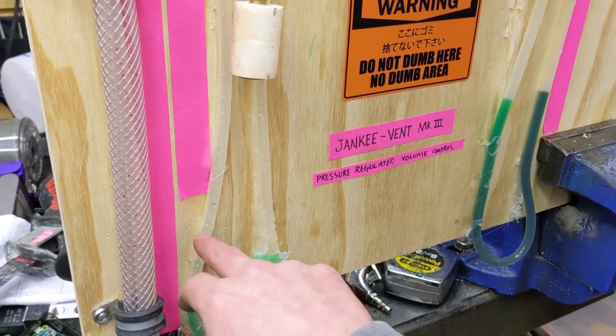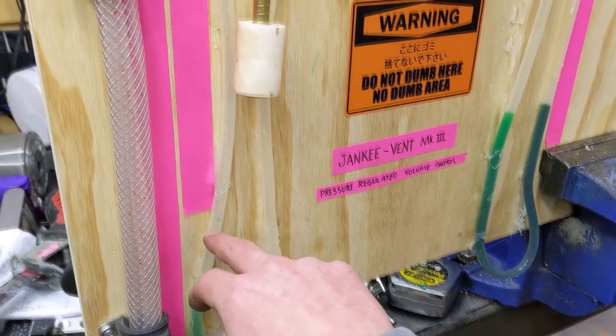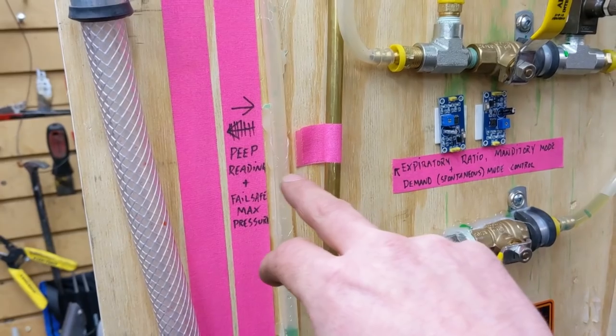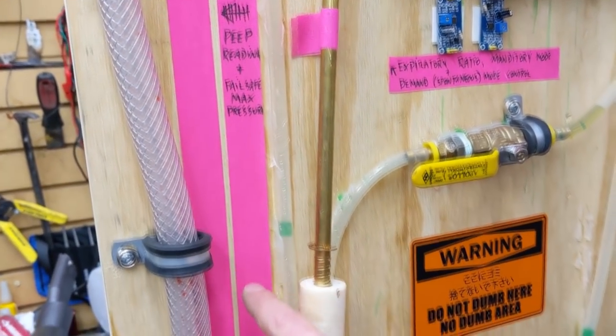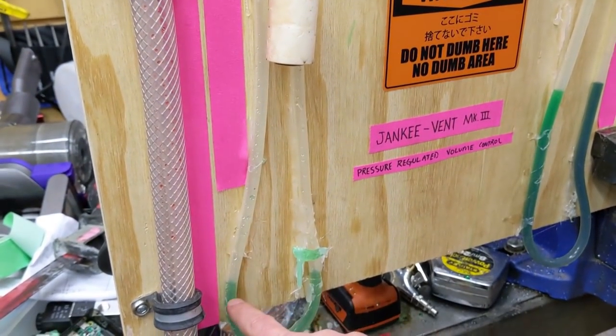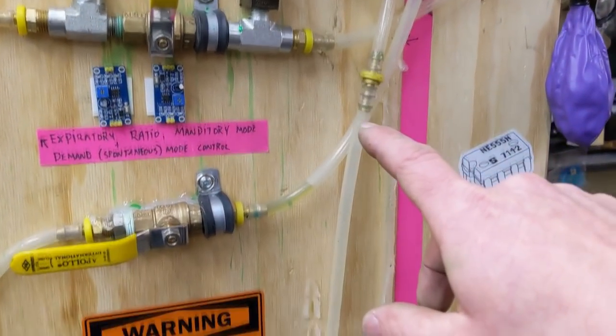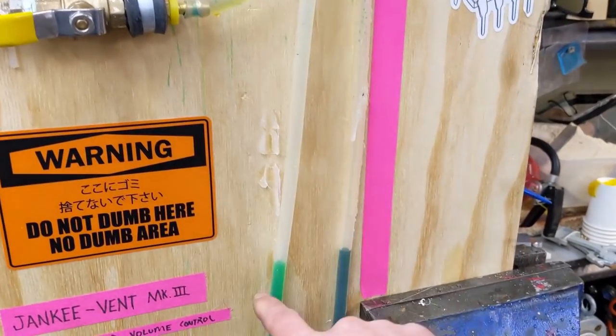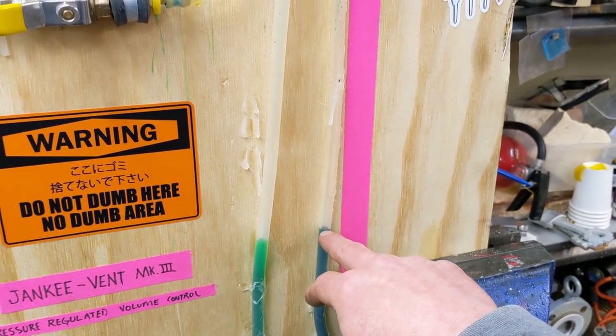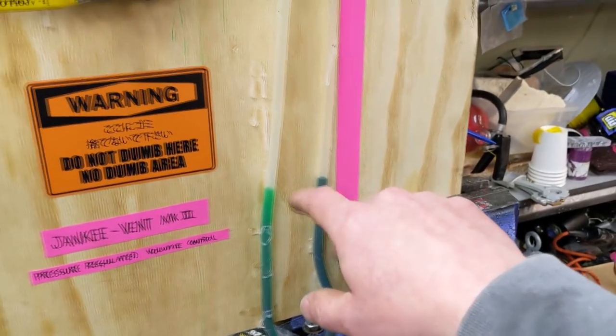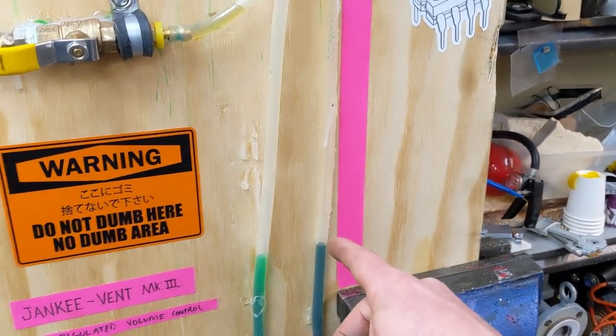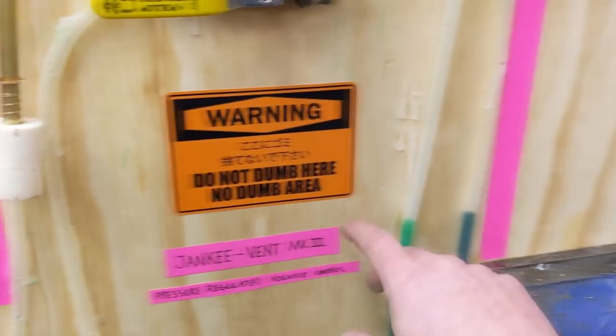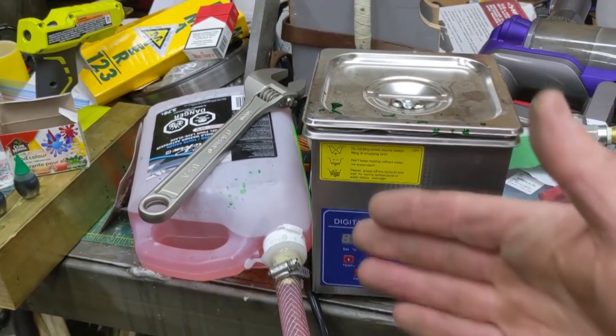It's the PEEP reading and it's also a fail safe max pressure. So depending on how much fluid you have in here, you have a max pressure of however many centimeters of water, the peak pressure and the platen pressure, we don't set it, but we monitor it here. So all we got to do, these are all manometers. So these are the visual readout, the visual feedback for all of these systems. Manometer one, manometer two, manometer three. I'm gonna run you through the series of operation.